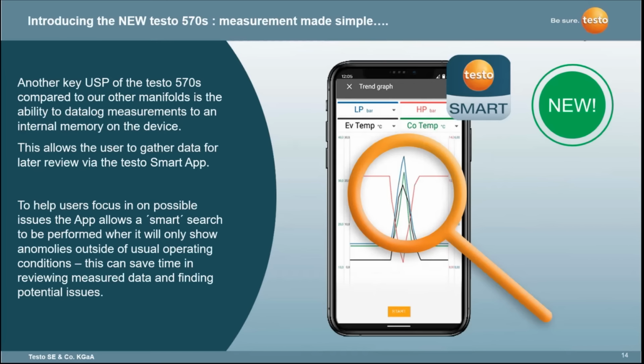So one of the key USPs of the 570s compared to the other manifolds in our range is that it's the only device that's got this ability to data log on site. So if maybe you have a system that has some sort of transient fault where you don't want to be waiting around hours looking at a screen to try and track what's going on, you can leave the 570s connected up to the system and then effectively set up a data logging routine that can run up to 72 hours. You have an adjustable cycle on that, so you can sample a minimum of 1 second intervals up to 60-second intervals, and you can be looking at your temperatures and pressures and also compressor currents.